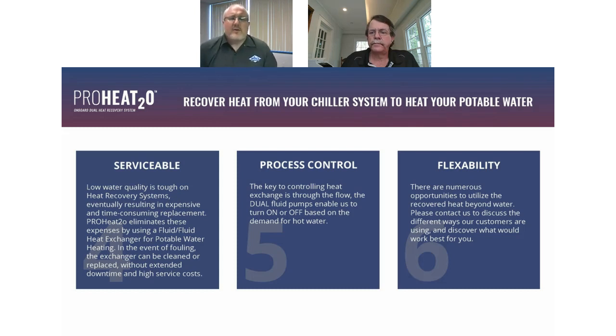It's serviceable. Low water quality is tough on heat recovery systems. I saw there was a boiler presentation earlier. We were talking about how you need to have a blowdown on the water because it can get minerals and deposits into the system. By separating the heat exchangers into a two-step heat exchanger, we're eliminating those high expenses that can come from having to service a failure on the refrigerant heat exchanger, and we're just looking at the heat transfer fluid to potable water heat exchanger as a potential failure point. What that means is a lot less expensive repair project if something happens. You don't need specialized refrigeration tools to make the change. You can essentially make the change with a pipe wrench and a bucket to catch the fluid that drains out.